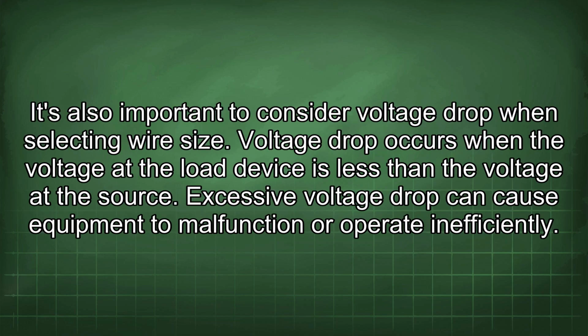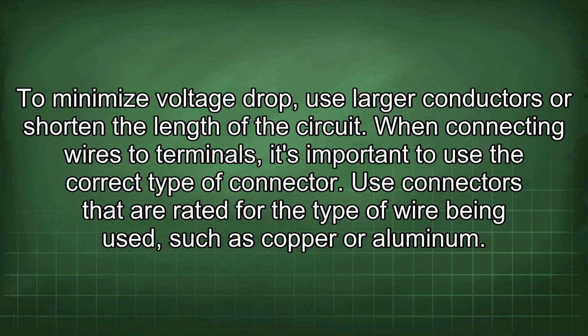It's also important to consider voltage drop when selecting wire size. Voltage drop occurs when the voltage at the load device is less than the voltage at the source. Excessive voltage drop can cause equipment to malfunction or operate inefficiently. To minimize voltage drop, use larger conductors or shorten the length of the circuit.